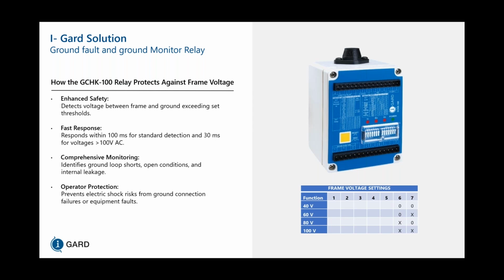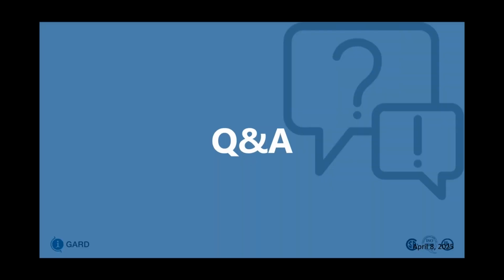On the front of the relay, we have dip switch settings, and we also have our map for the dip switches directly on the relay, so it's very user-friendly. Our frame voltage settings are between 40 to 100 volts with 20 volt steps in between, and these are configurable as well on the dip switches. At the top, we have the fuse portion, which can be replaced if a fuse gets blown within the field. So if there are any questions, feel free to ask, and I'll be covering those right now.